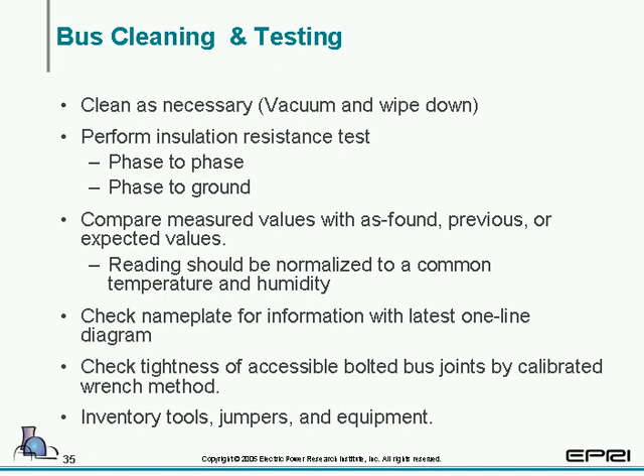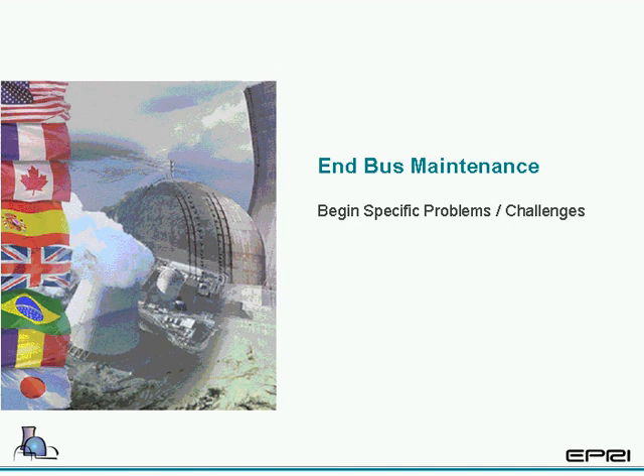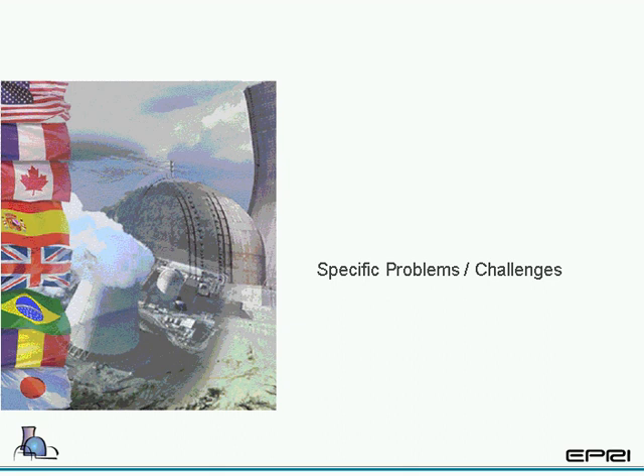After you do that, then you perform insulation tests. You do phase-to-phase and phase-to-ground, pretty similar to what you do for the breaker. Then you want to compare those values to what is either considered expected or, if the manufacturer gives some sort of values, to those. And keep in mind that temperature and humidity will affect your values. The last thing you want to do is inventory your tools, jumpers, and equipment before you close up the cubicle. And that ends bus maintenance.